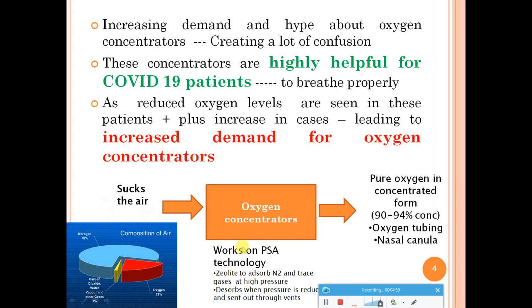They will suck in air, and they have certain adsorbing materials within them which are very specific, which will adsorb all other gases apart from oxygen. Once they adsorb all other gases apart from oxygen, you can concentrate it and send it out. Finally, whatever other gases they have adsorbed, they can desorb. That is nothing but once it gets attached onto the surface, you can remove it from the surface by varying the pressure. At high pressure it adsorbs these gases, and when you decrease the pressure it desorbs these gases. Once the gases are desorbed, they can be sent out through the vent. Nitrogen and other gases which we saw here are sent out, whereas oxygen is sent for the application, that is, for the patient who is suffering from COVID.